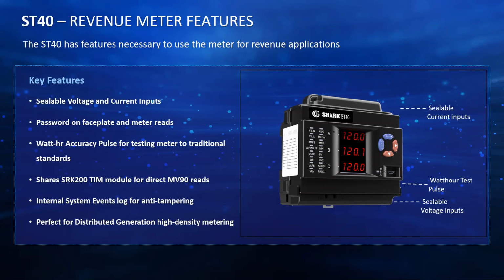You can set passwords on the faceplate and the meter reads if you want to for security purposes. The ST40 is also compatible with MV90, so it can be used for utility billing applications. There's an internal system events log for anti-tampering. So if you have security enabled on your meter and then someone goes and tries to tamper with it or break into your meter, the meter will log that as a system event that happened with a timestamp, so that you can later go in and analyze if there was any type of security breach that someone attempted.